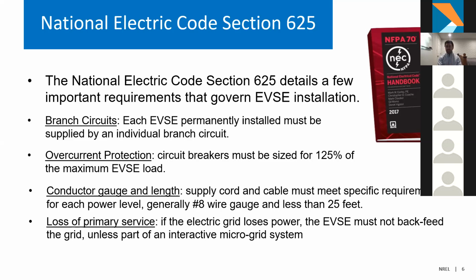And for these EVSE devices, you need to size them 125% of the maximum EVSE load, and that's by a current rating. So what's really common for level 2 units is to operate at 240 or 208 volts, but the current on those is typically 32 amps. So if you're sizing for 125% of that load, you would need to get a breaker that's rated for about 40 amps.